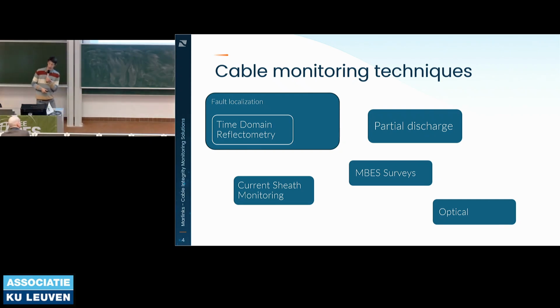There's quite a bit of monitoring techniques out there. Jerry already mentioned some of them: partial discharge is one, surveys, MBES surveys, sub-bottom profilers as well, current sheath monitoring mainly on land cables. You also have a whole bunch of fault localization techniques, time domain reflectometry being the most commonly used.